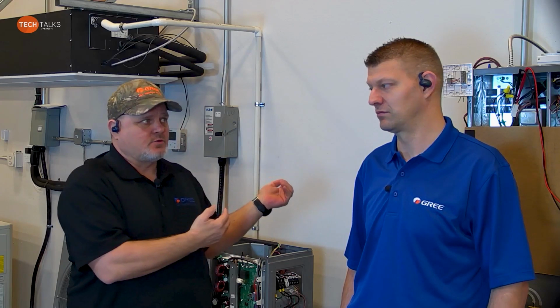There's advantages to using the GREE controller and disadvantages. So it depends on how you look at it. It's not what I look at, it's what you look at, right? So what I'm saying is the advantage is you're not going to have to set dip switches for blower operation, and you're going to get more of a variable speed with the GREE controller. If you use 24 volt, now you're going to have to set the dip switches in order to get proper airflow for 2-ton, 3-ton, 4-ton, and 5-ton. Okay? It becomes a fixed CFM at that time. So there's the advantage with the GREE controller. You get more of a variable operation with the system.